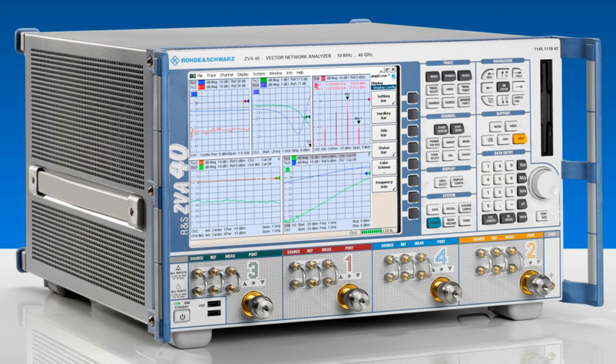The SOLT calibration method is less suitable for waveguide measurements, where it is difficult to obtain an open circuit or a load, or for measurements on non-coaxial test fixtures, where the same problems with finding suitable standards exist. TRL, through reflect line calibration. This technique is useful for microwave, noncoaxial environments such as fixture, wafer probing, or waveguide. TRL uses a transmission line, significantly longer in electrical length than the through line, of known length and impedance as one standard. TRL also requires a high reflection standard, usually a short or open, whose impedance does not have to be well characterized, but it must be electrically the same for both test ports.